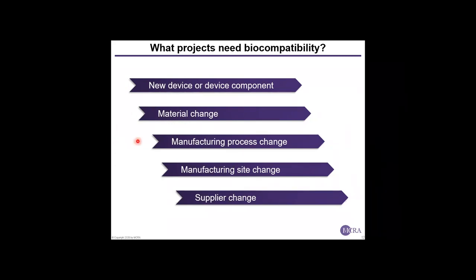These include manufacturing process changes, changes to your manufacturing site, and even supplier changes. And I want to take just a second to talk about supplier changes because they're often thought about as minor, and they're very common in the medical device industry. And often these supplier changes don't come by choice. Sometimes availability of suppliers is what drives these supplier changes. But even though these changes are common and often thought of as minor, they can be associated with a substantial regulatory burden. In fact, this has become one of the top pain points of our clients, and many clients are blindsided when a regulator asks them for a massive amount of justification and potentially test data to support those supplier changes. So just some examples of how common biocompatibility can come up in a regulatory submission.